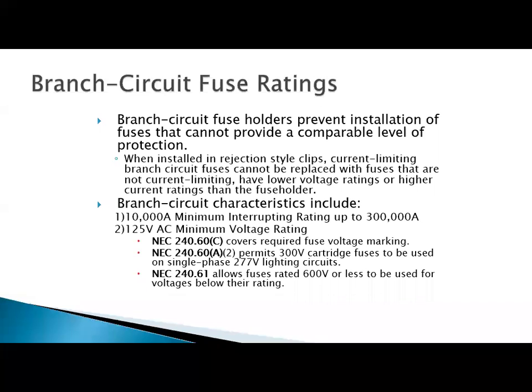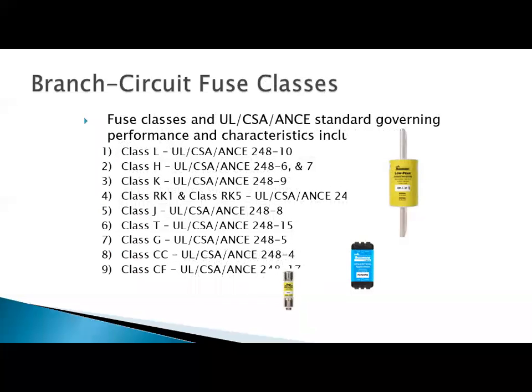So we're not going to be able to put in a higher ampacity fuse than what is needed for that circuit. But I really want to stress this, that when we replace a fuse, we want to make sure we replace that fuse with the exact same fuse that came out. Because the clearing time is going to impact my incident energy on that circuit.